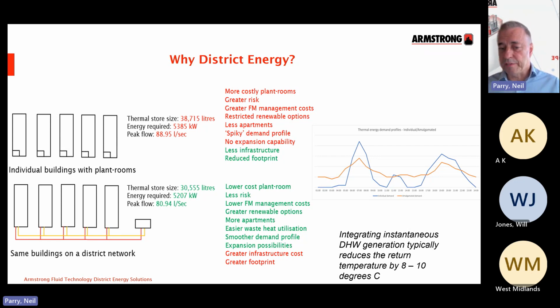And finally, if you add instantaneous hot water generation into the mix, then typically you tend to reduce your return temperature by, on average, something around 8 to 10 degrees C. And what we'll see a little bit later on is the advantages that come out of having a greater delta T or a lower return temperature. Those two phrases are pretty much interchangeable, but we'll look at that in much more detail as we move on.